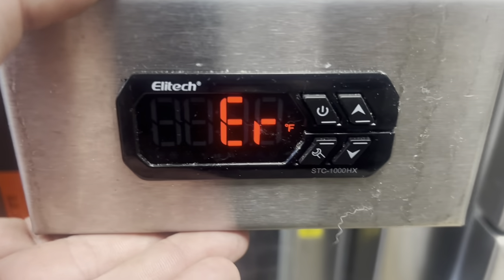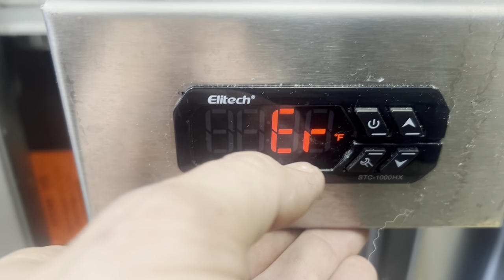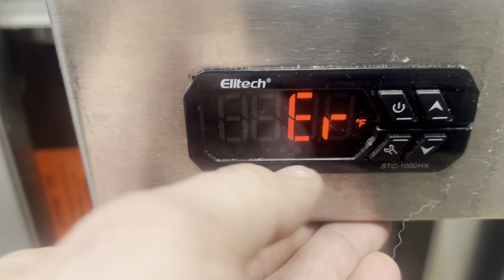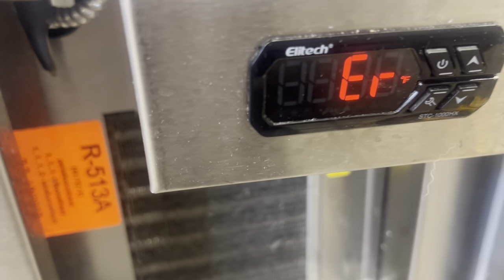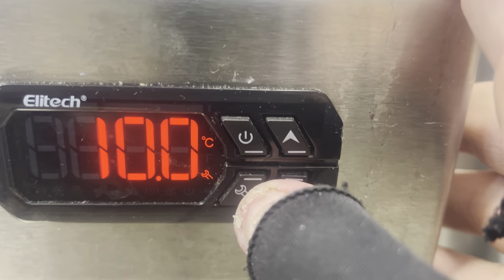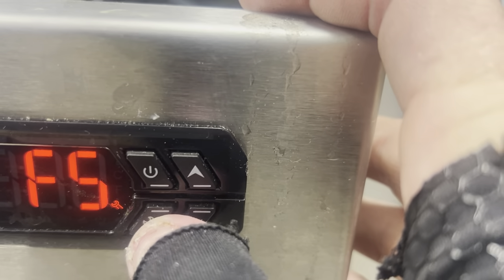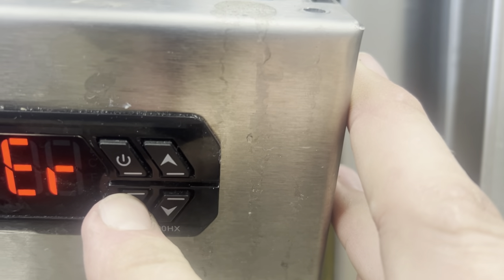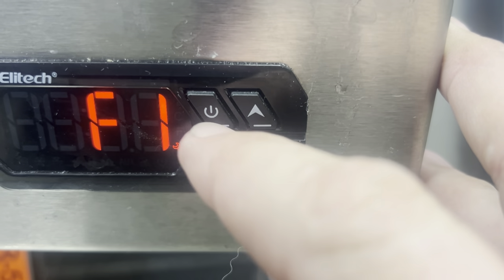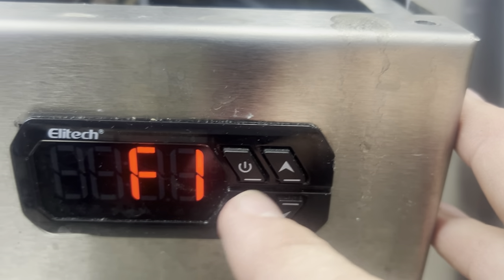We've got this freezer unit with a controller that reads the temperature and then kicks into error — it reads this, hits the snowflakes for a second, and runs. It's either a bad controller or bad probe. Before I disconnect it I want to look at the settings. Oh, Celsius — I think that's five, zero. Er is temperature probe. It's just not holding any setting. It's dead.